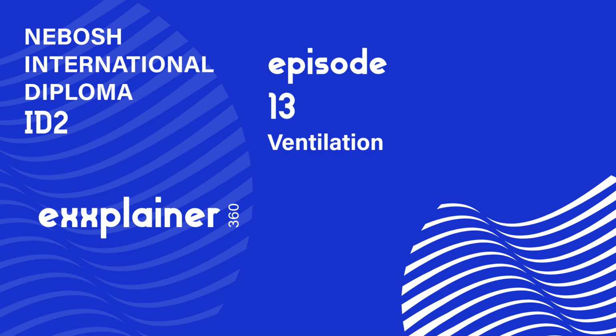This is incredibly detailed. So you've designed it, installed it. How do you know it's actually working correctly day to day, year to year? That's where the crucial final step comes in. The thorough examination and testing, often called TExT. And this is a legal thing. Absolutely. New systems need formal commissioning tests to prove they meet the design specs. Existing systems need regular testing by law. In the UK, under COSHH, it's typically at least once every 14 months.